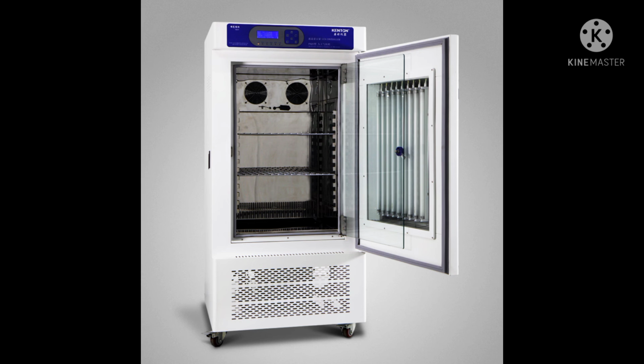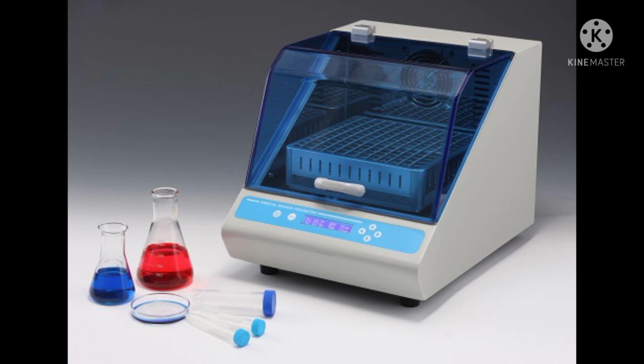Refrigerated incubator. For incubation at sub-ambient temperature, the incubator is equipped with a modified cooling system with heating and cooling control. This type of incubator is called a cooling incubator. In the refrigerated incubator, heating and cooling control must be precisely balanced. Shaking incubator. The thermally controlled shaking incubator is another equipment used to cultivate microorganisms. Its advantages are that it provides fast and uniform heat transfer to the culture, and better aeration for faster growth. However, this incubator can only be used for liquid culture media.